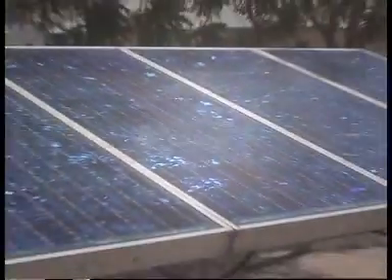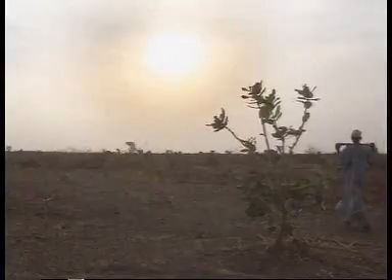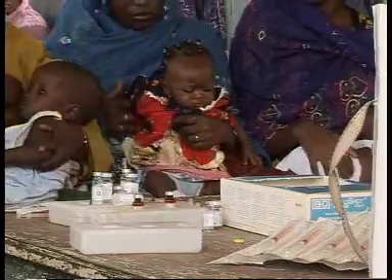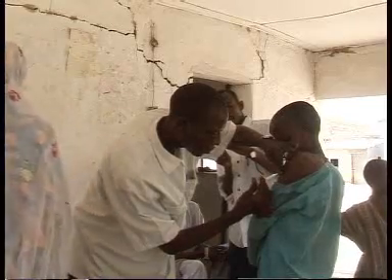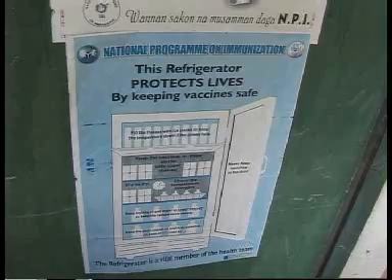But one man's vision to harness the sun's energy is already making a difference. With the amount of sunlight available in Nigeria, it seemed there was an excellent opportunity to do something. The National Programme on Immunisation covers quite a large number of preventable diseases, such as polio and diphtheria. The problem really is that vaccines have to be kept in a controlled temperature within limits of two degrees centigrade. The solar fridges play an important part of that at the end of the chain in remote areas.